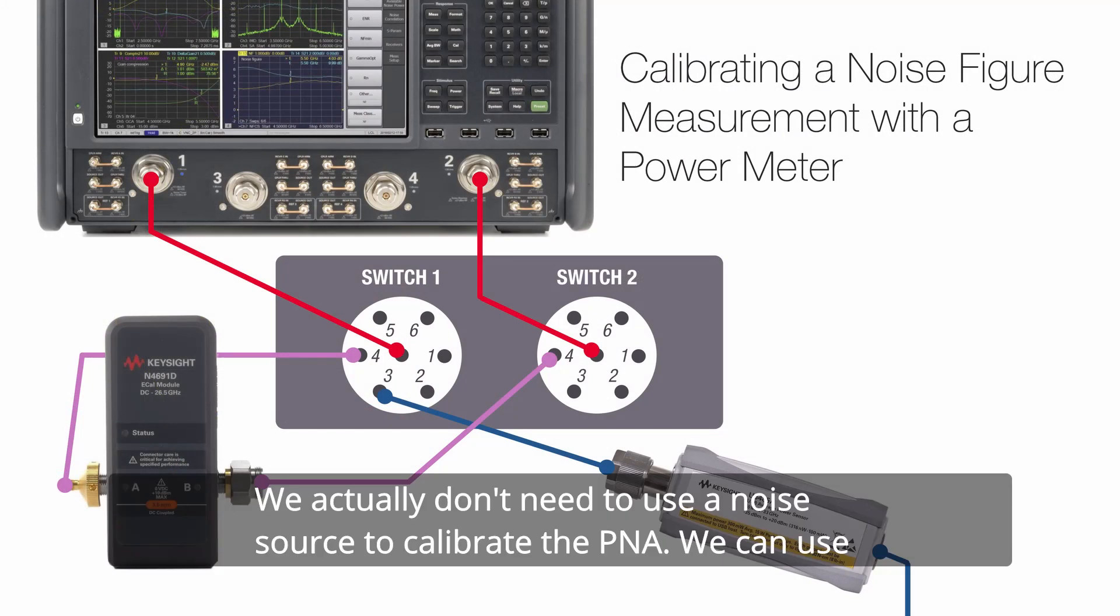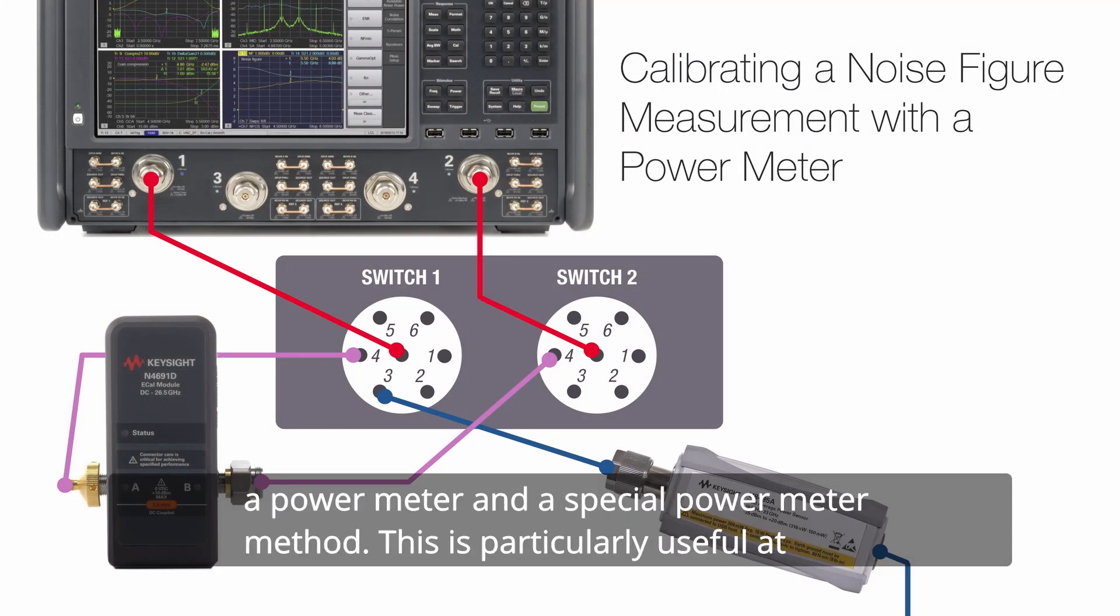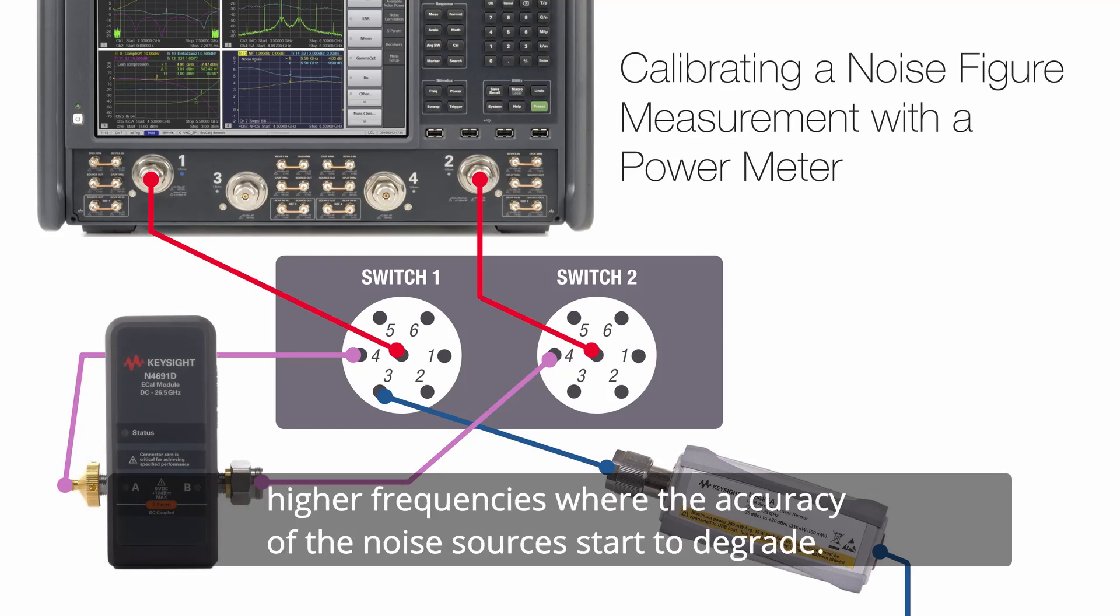We actually don't need to use a noise source to calibrate the PNA. We can use a power meter in a special power meter method. This is particularly useful at higher frequencies where the accuracy of the noise sources start to degrade.